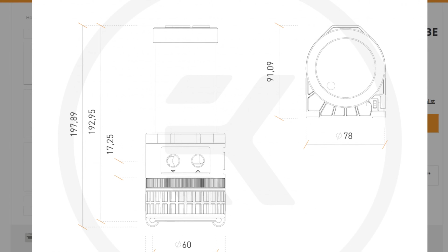The D5 pump is a hemispherical sealed motor, so we use the power of magnetics. The thing that moves the water is moved magnetically, so the part of the motor that the water is in contact with and the part that the electronics are in are physically isolated from one another. There's actually a ceramic bowl, and a hemispherical impeller sits in the bowl. It relies on water entering the bowl and lubricating things and keeping everything running, and also helping cool the electronics. Electromagnets around the perimeter of the ceramic bowl move the impeller because of the permanent magnets installed in the motor.